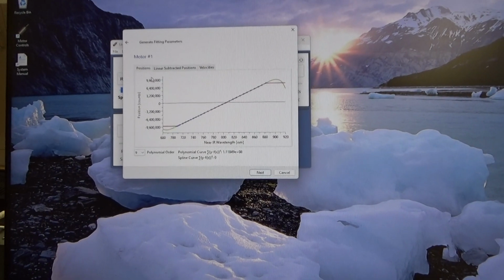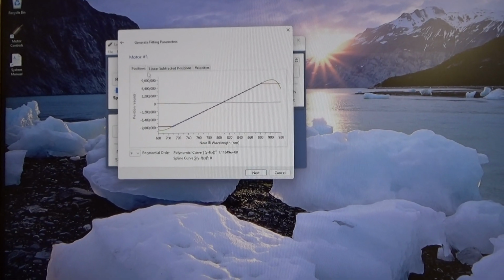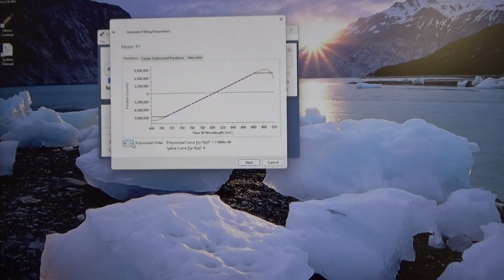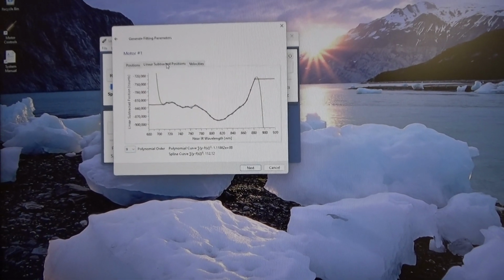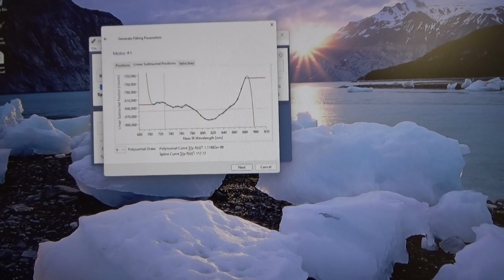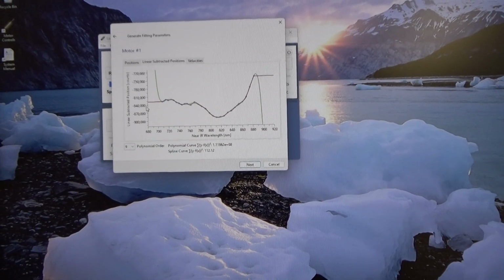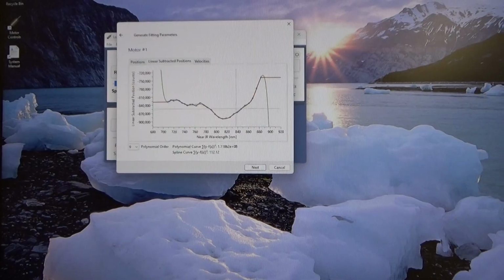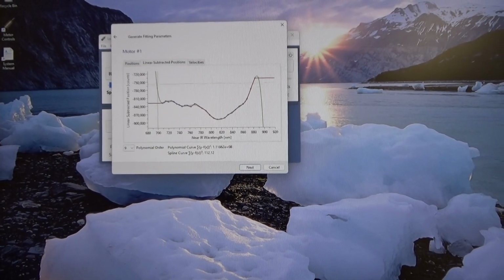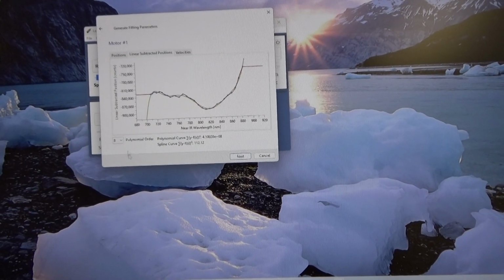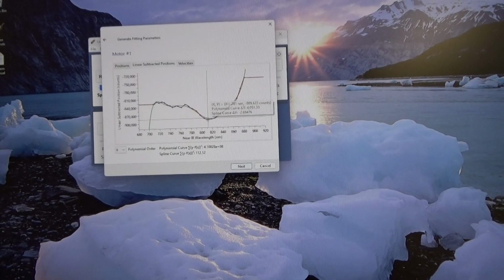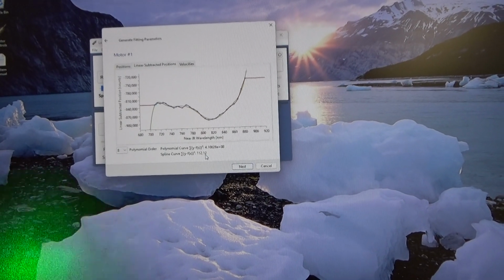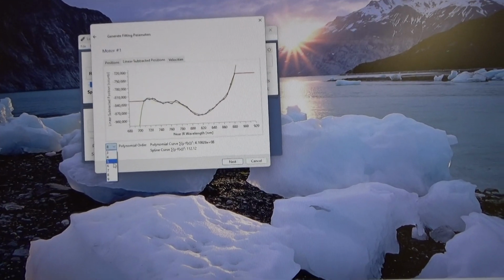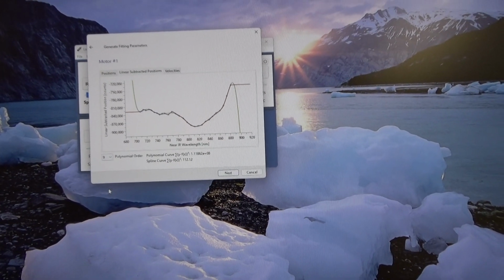And you'll be given the option for each one of the motors as to what polynomial order you'd like to use for the data. So if I can go to linear subtracted here, I can see the curvature. The red line is a spline fit to the data, and the green line is a polynomial fit. And so I can change the polynomial fit and observe what that does to the actual curve that is going to be followed by the motors, and what the statistics say about that. Usually a ninth order polynomial is best fit.